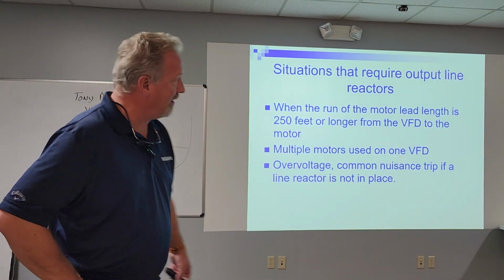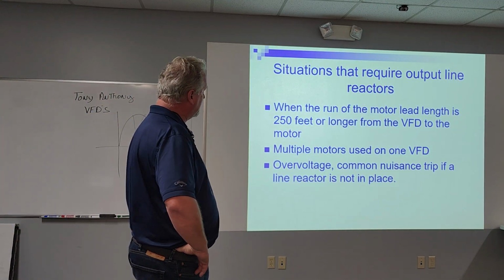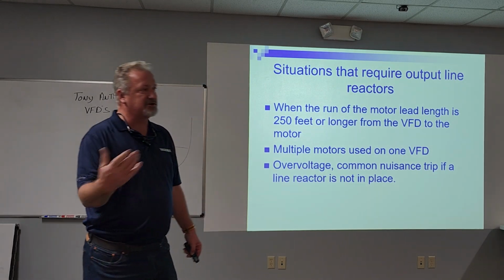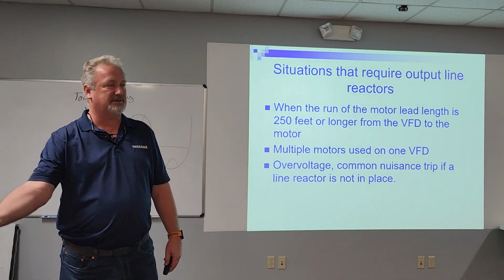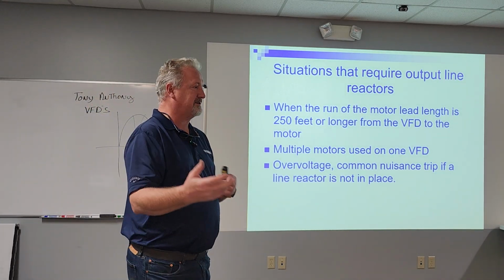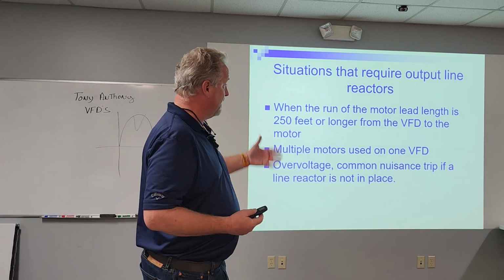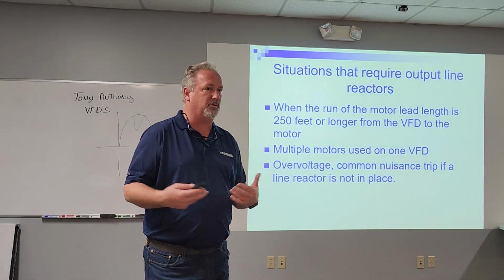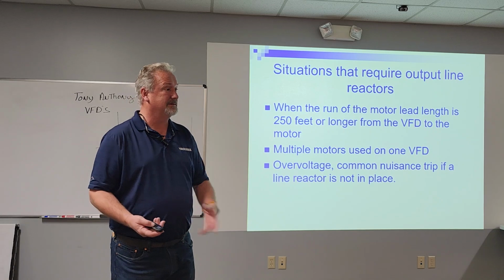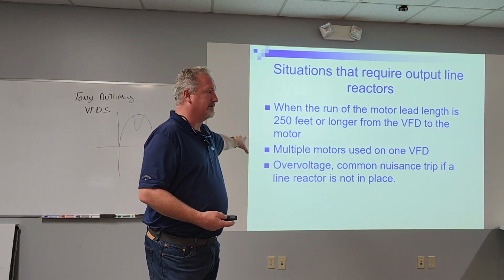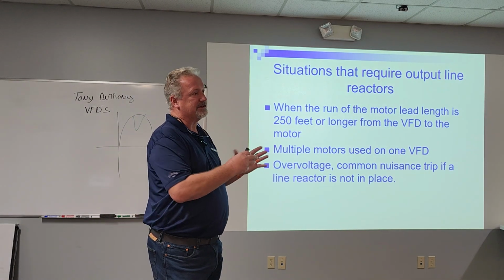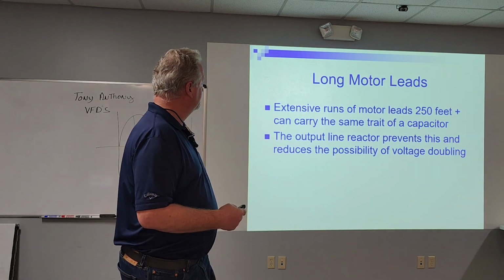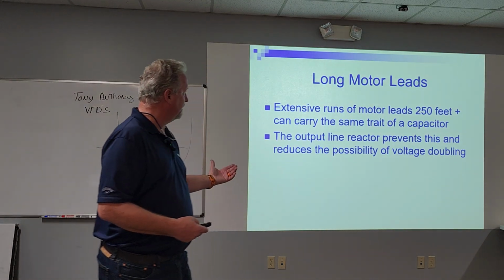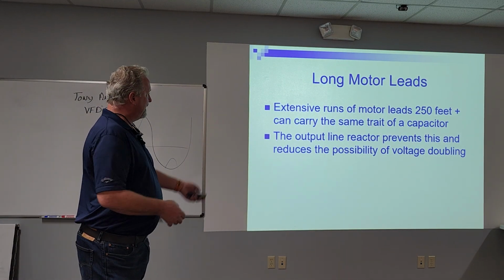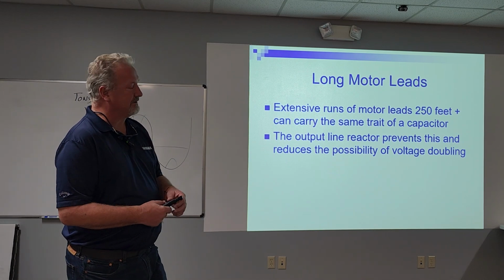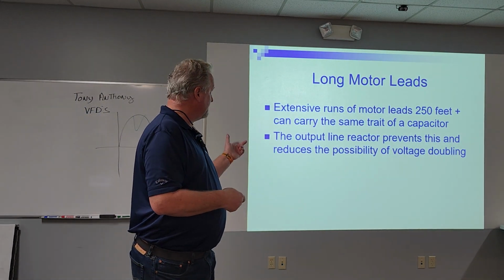All right. Now, also, if the motor gets too far away, you may start getting nuisance trips on the drive. You get what we call voltage feedback. You can get all kinds of stuff happening. If you have multiple motors and your drive just starts tripping occasionally for no reason and you can't figure it out, a load reactor may just clear that up, especially if the motor is any distance away. Long motor leads, 250 feet. It kind of carries the same thing as a capacitor, and that's what can cause troubles, and that's when you would use one.